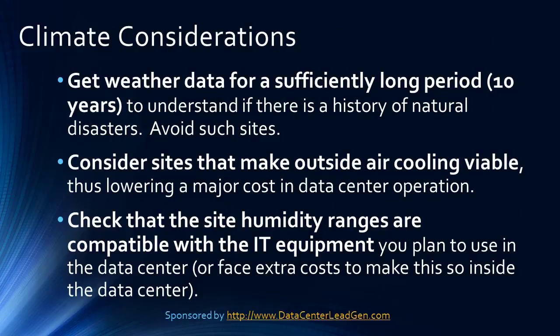Climate Considerations: Climate and natural conditions can affect the quality of a site for a data center in many ways. Get weather data for a sufficiently long period — 10 years — to understand if there is a history of natural disasters, and avoid such sites. Consider sites that make outside air cooling viable, thus lowering a major cost in data center operation. Check that the site humidity ranges are compatible with the IT equipment you plan to use, or face extra costs to compensate inside the data center.